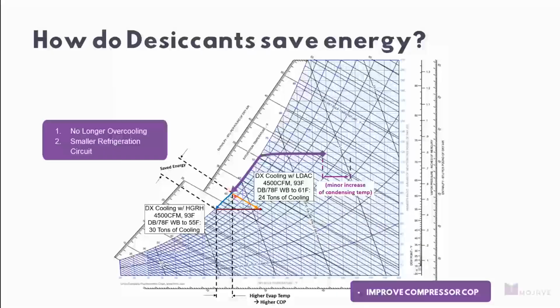And then as a final note, the distance you travel down this enthalpy line is a function of the concentration of liquid desiccant. So if you want to dehumidify further, you reset how much heat you put into that desiccant on the regeneration side. That'll up your concentration and allow you to ride your enthalpy line further. And if you need less dehumidification, say it's a part load day, you back off on concentration, which allows you to travel a shorter distance, not dehumidifying as much. And this is how we're able to actively tune our desiccant system to be, frankly, as efficient as we could possibly be at any given point in time, whether it's a full load day or a part load day.